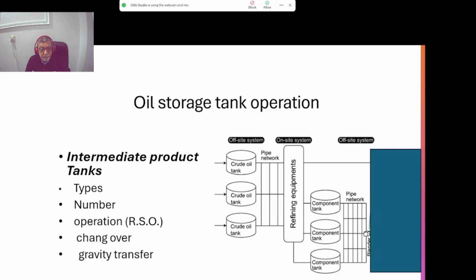fixed roof tanks. The number of tanks for each product depends on the capacity of the unit, maybe one tank, maybe two tanks, but at least two tanks to change over from one to the other. In emergency cases, we can use other tanks. The changeover from one tank to another follows the same procedure we follow for crude oil: we have to open before close. We can also transfer from one tank to another by gravity, without pumps, until the level is the same in the other tank. We call this gravity transfer.